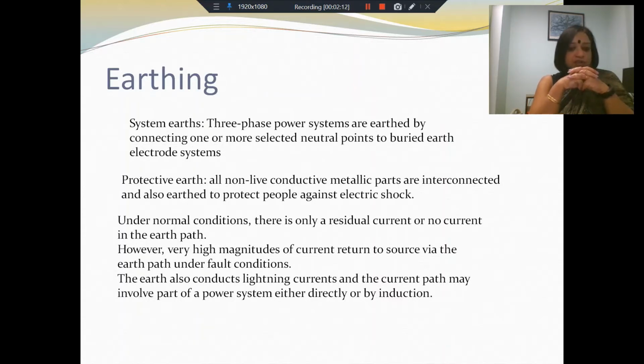Also, if you have lightning, in that case too the lightning current will flow to the earth conductors. It may be a direct strike, in which case a direct current will tend to flow through the earth paths, or even if there is a lightning strike in the vicinity of your system and that results in induced overvoltages at certain points in your system, that will cause high currents to flow through the earth path. So these are the situations which need attention. We have to make sure that even under fault conditions, lightning strikes or transients, the earthing is functional and no high potential rises occur, and no damage is caused to the system or personnel.